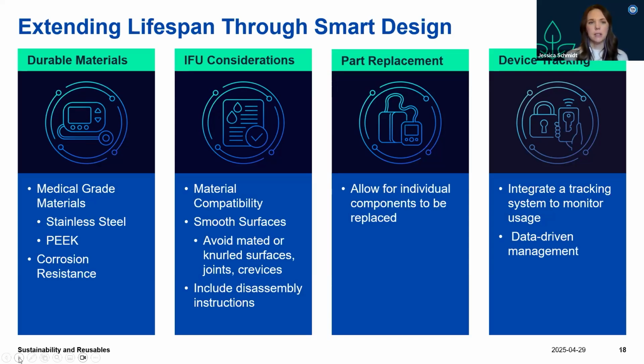Moving on to part replacement. Rather than disposing of an entire device when one component wears out, smart design allows for individual parts to be replaced. This can significantly reduce waste and cost over time. And finally, device tracking: integrating a tracking system that helps monitor usage and maintenance history. So you can use data-driven insights to make informed decisions about when a device needs servicing or replacement, ensuring both efficiency and patient safety. So by making intentional design choices upfront, we can significantly enhance both the lifespan of the devices and the sustainability of our healthcare systems.